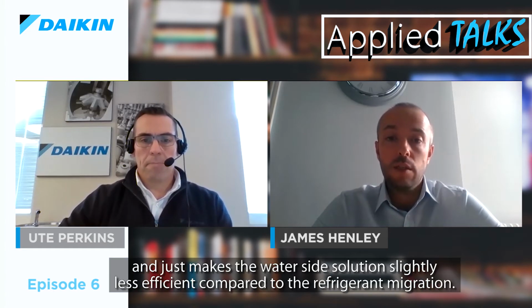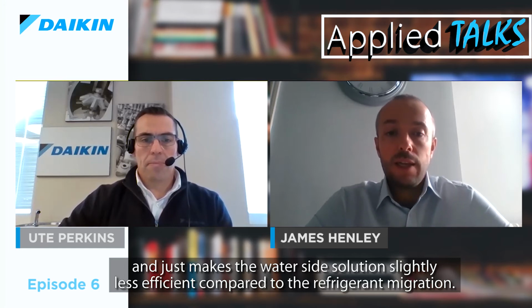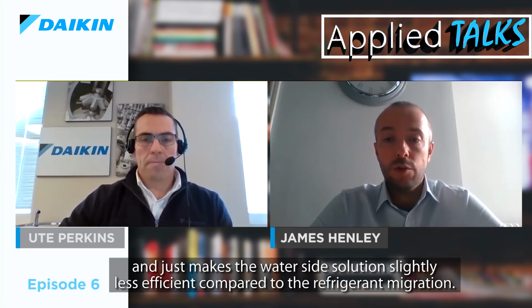There is the traditional waterside free cooling technology available in the market with an inline dry air cooler or a dual refrigerant and chilled water coil. And whilst this free cooling is efficient, the system typically requires glycol content of up to 30% or a free cooling separation plate heat exchanger. And this reduces the overall system efficiency. Also, considering the additional free cooling water coil pressure drop increases the pump power in the system, and the increase with the dual coil in the fan static pressure drop again increases the fan power input and just makes the waterside solution slightly less efficient compared to the refrigerant migration solution.